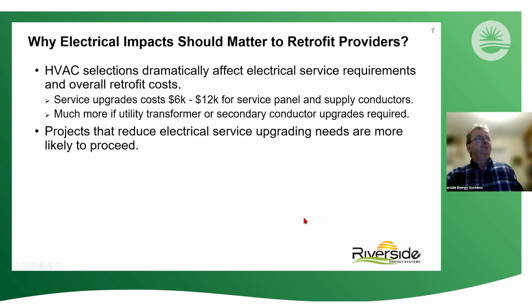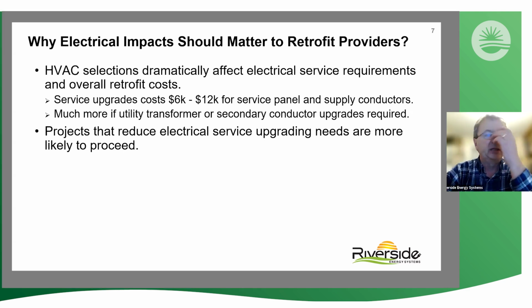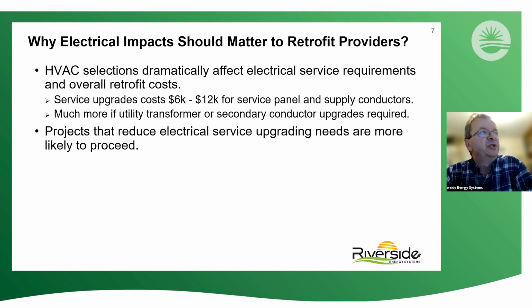So why do electrical impacts matter when we're doing a retrofit? Well, typically when we electrify HVAC in particular, it can dramatically affect the electrical demand, which can have a big impact on service requirements, increasing costs very significantly. Projects that require electrical service upgrades are less likely to proceed. Conversely, if we can reduce the need for those upgrades, they're more likely to go ahead, and we're more likely to achieve our retrofitting goals at large.